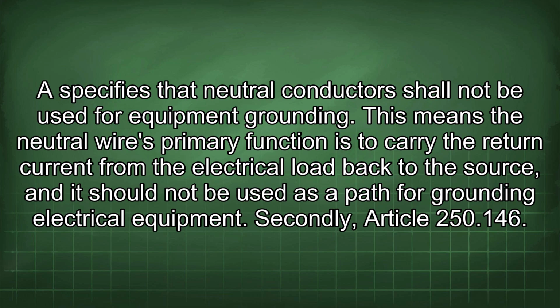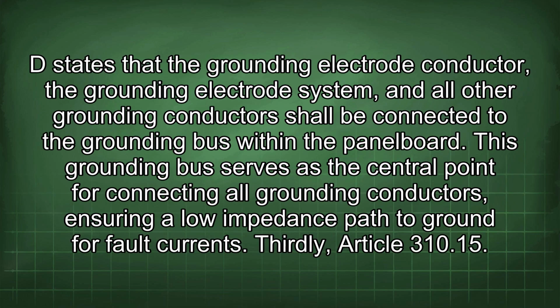Secondly, Article 250.146 states that the grounding electrode conductor, the grounding electrode system, and all other grounding conductors shall be connected to the grounding bus within the panel board.